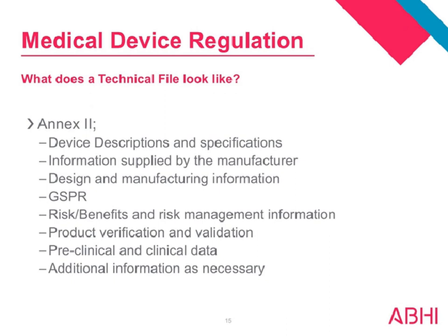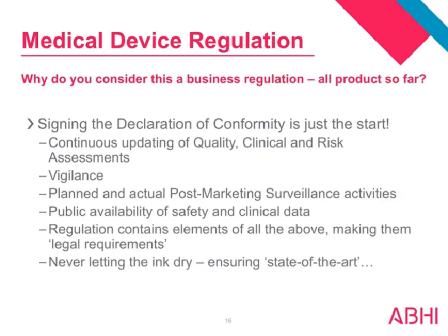how you've achieved verification of your product, and how you validate that the manufacturing processes are consistently making that product. And then again, importantly, one of the big drives within the MDR is how you then demonstrate compliance against both preclinical and clinical data, safety and performance. And then there may be other additional information that you may want to include within your technical file. For example, how you're dealing with predicate devices, whether you're actually looking at your clinical evaluations, where you're getting your data from, that sort of level of information.